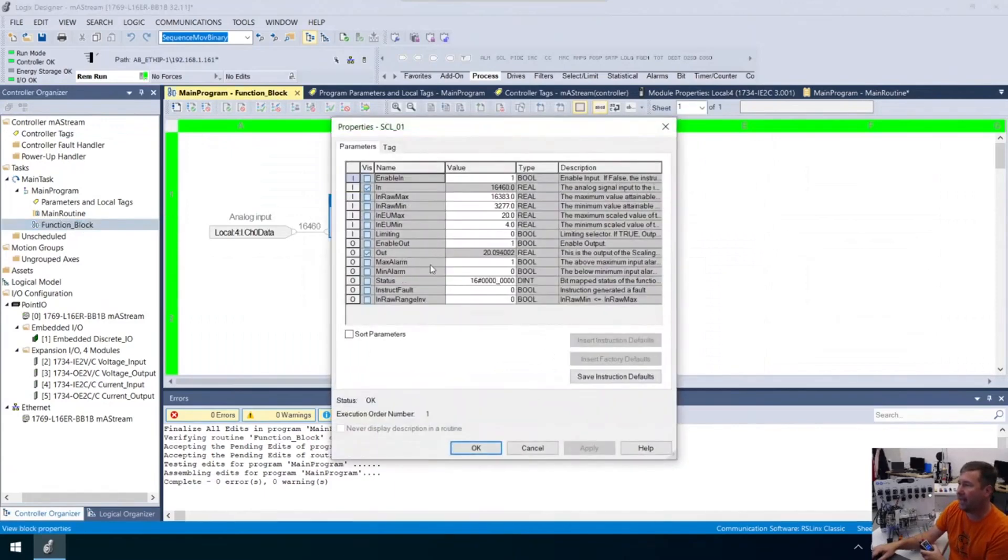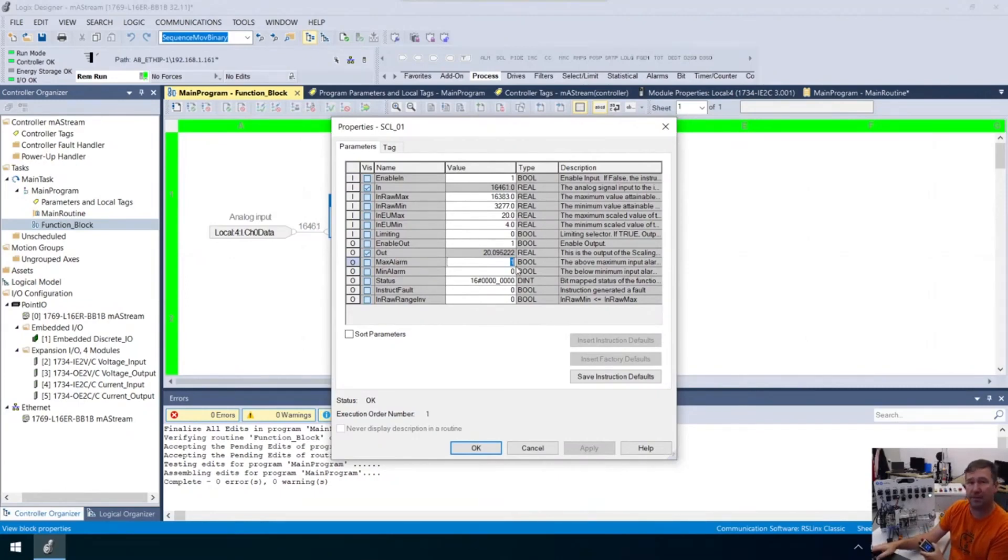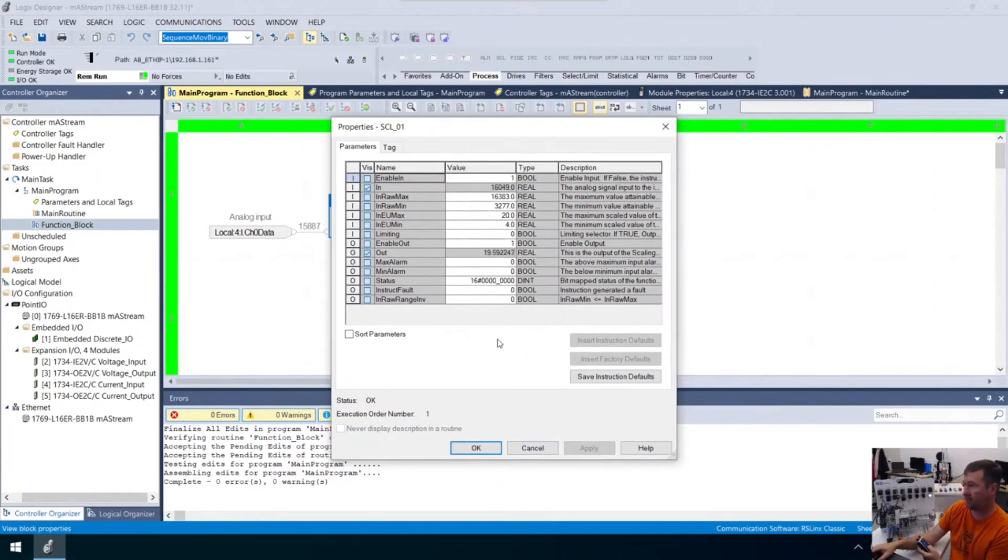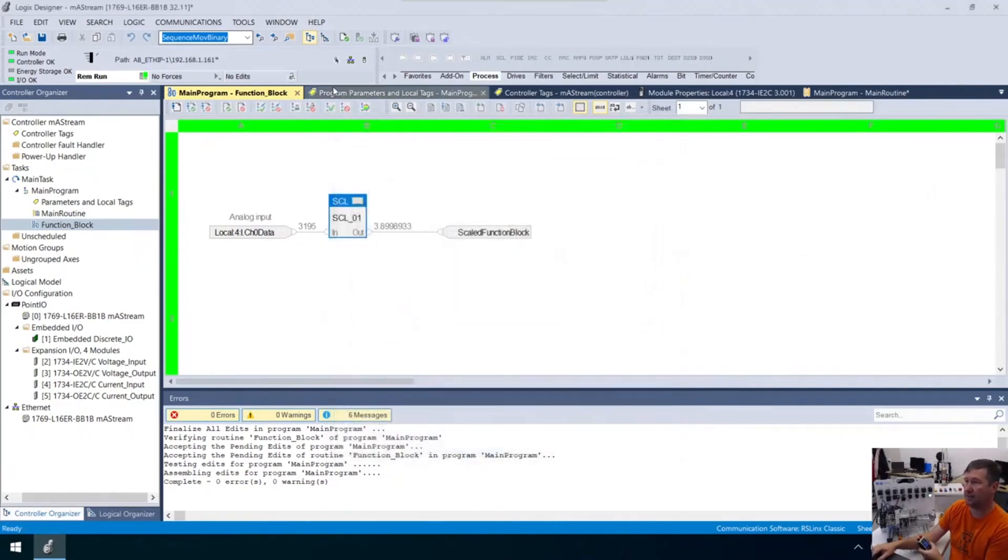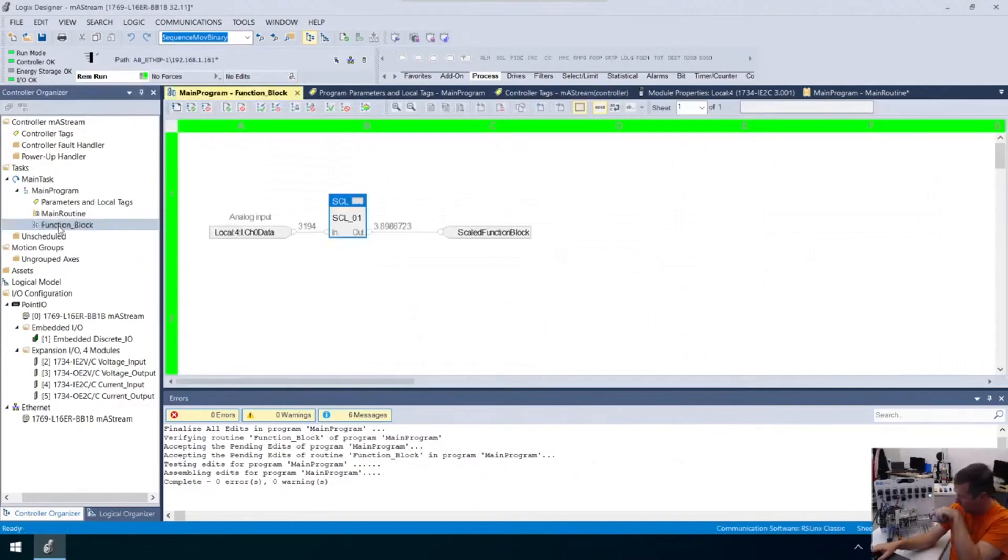We have this max alarm and min alarm. Notice our max alarm is now a one. We can use this as an alarm if our sensor is above 20, because typically above 20 means something is wrong with your milliamp circuit. If we go down below 4, we get a minimum alarm. That's going to let us know that something's wrong. You can see they're sticking right together.